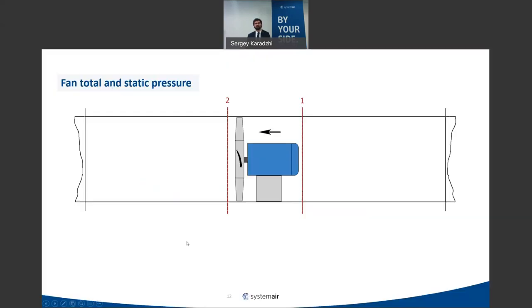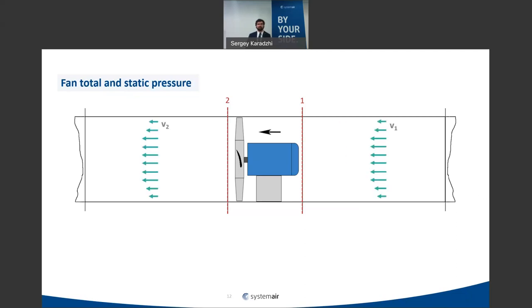When a fan is installed in a duct system, customers are sometimes confused about total versus static pressure. When you calculate your duct system losses, you get the difference of static or total pressure on the inlet and outlet of the fan. If the duct diameter is the same on both sides, the dynamic pressure is equal on both sides, meaning the difference in static pressures equals the difference in total pressures.